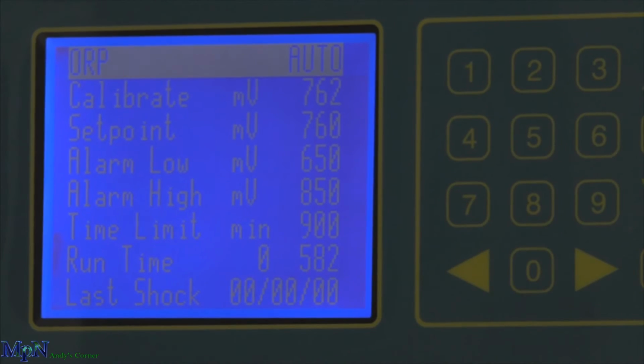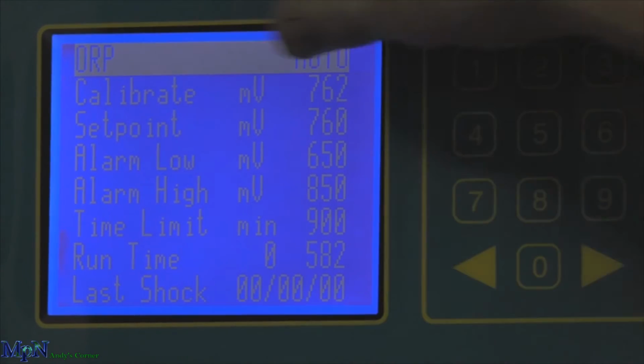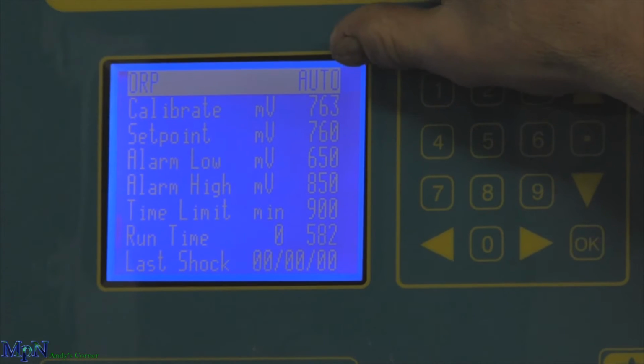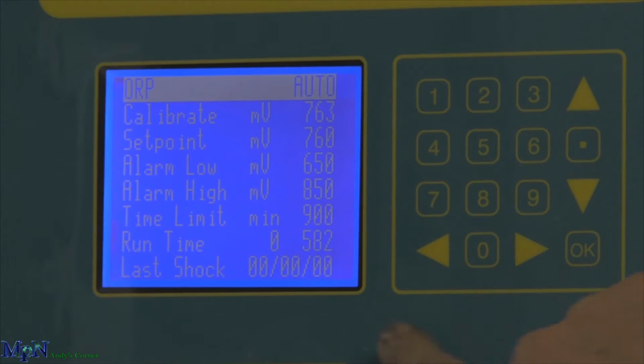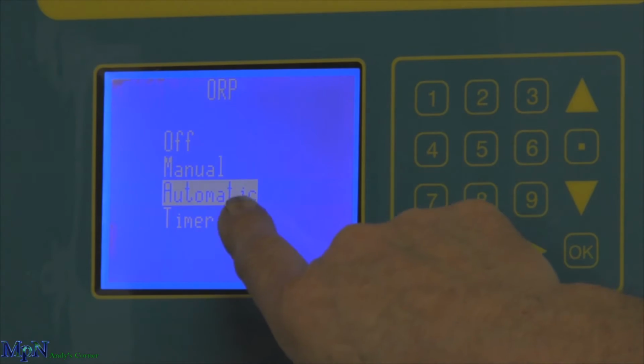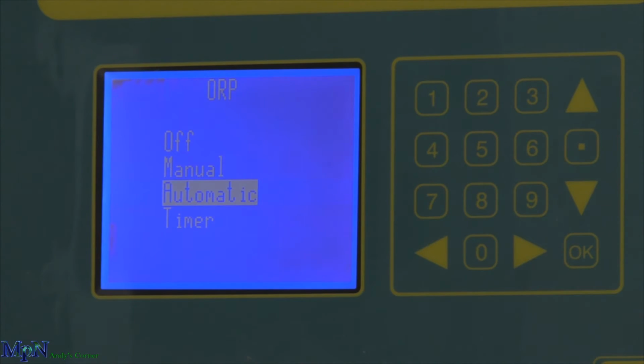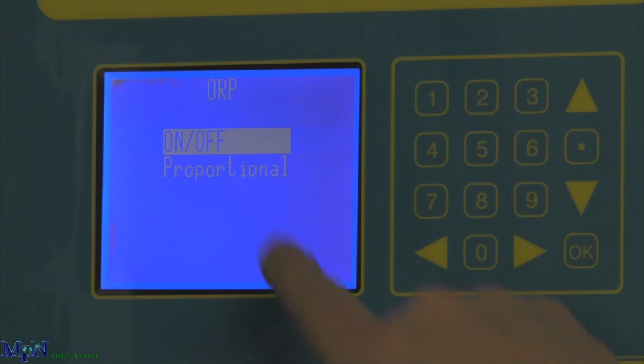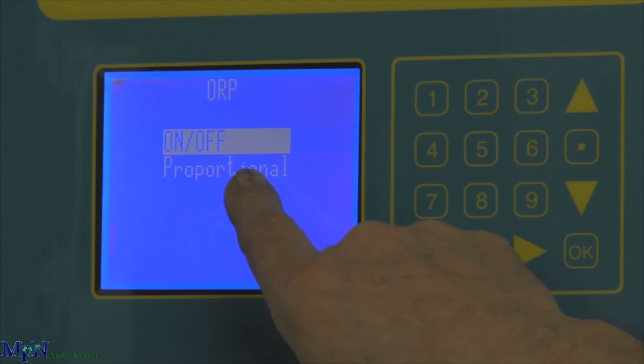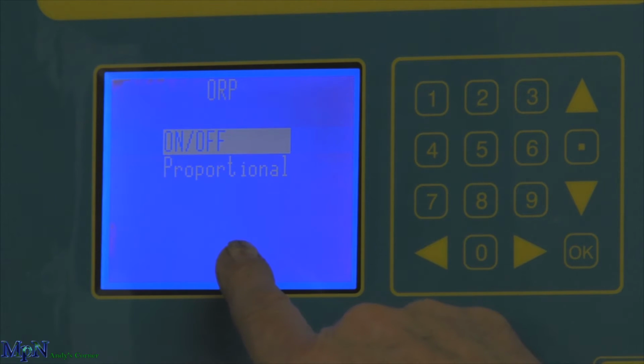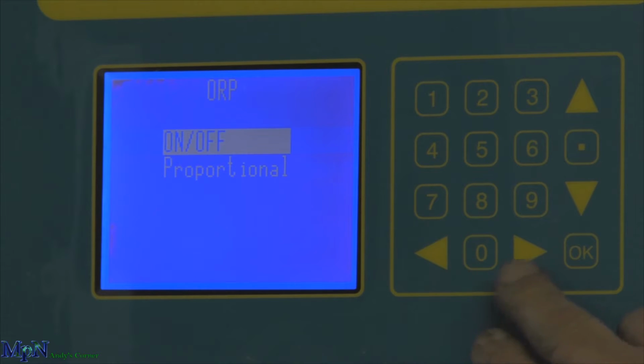All of these menus are similar. The only difference is the top heading. This is automatic, which if I right arrow in, we can either do automatic, manual, or off. That's if you have to turn off because you're shocking. If we right arrow in on automatic, we have on-off, which means it's going to turn on and off on demand. Proportional means it'll pump for a little bit, wait, let the water and the chlorine mix for a little bit, then pump a little bit more, trying to eliminate some of the overshooting. A lot of that is on the smaller bodies of water.